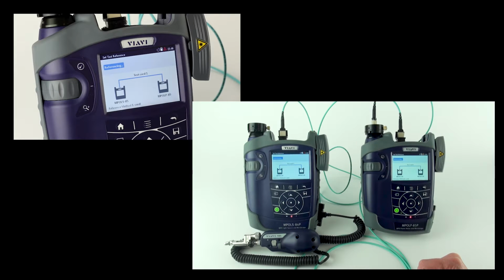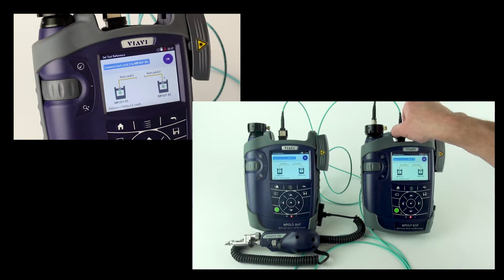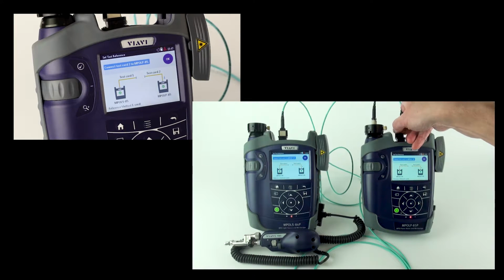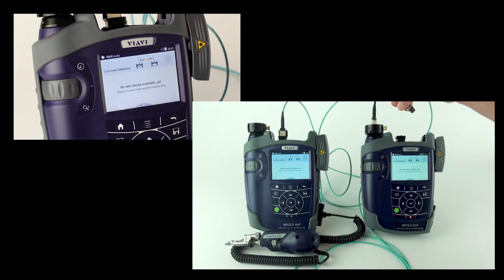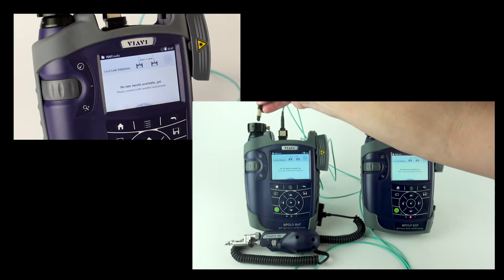It shows that the two are connected together, and it says referencing, and it takes a few seconds to set all the levels, and then it tells you that the reference has been successfully completed, and it tells you what to do next. You notice that it's telling you to connect the test cord to the MPOLP, which means that I disconnect my fiber from my power meter, never from my source. If I disconnect from my source, I need to re-reference.